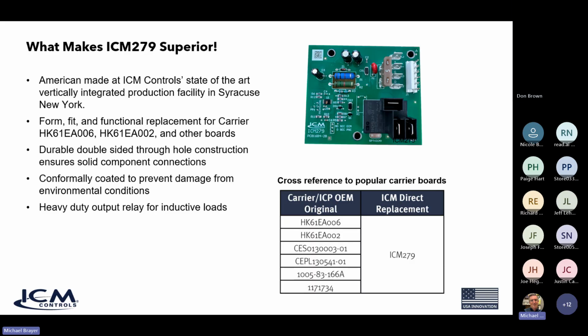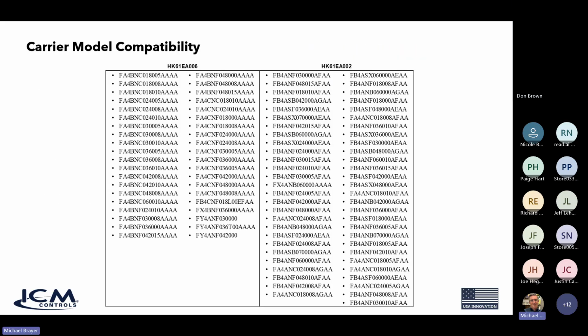We do conformally coat to prevent damage from environmental conditions. So any effect of moisture or dust or dirt or anything won't contaminate our board. And we have a heavy duty output relay for the inductive loads. This is not an all-inclusive list, but I just wanted to portray to you how many of the Carrier models are compatible with the two of the primary boards that we cross over to. And when you consider all the other boards, there's over 100 applications for the ICM279 to fit a Carrier product.